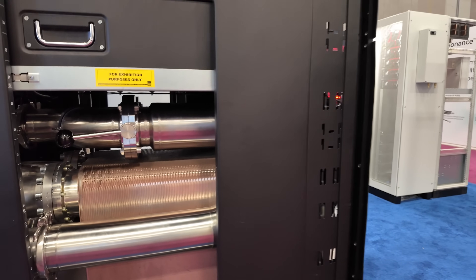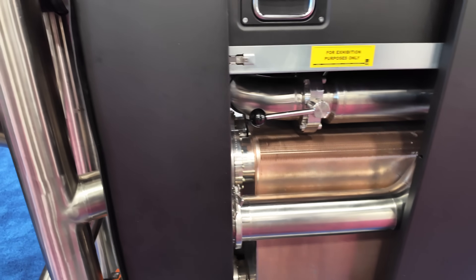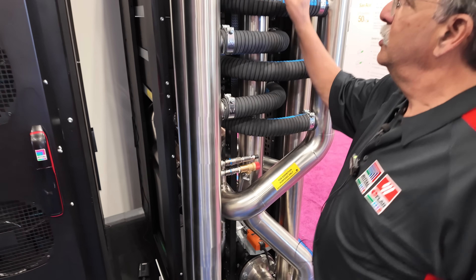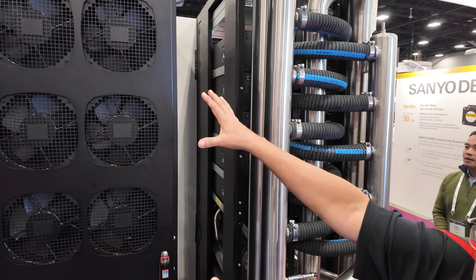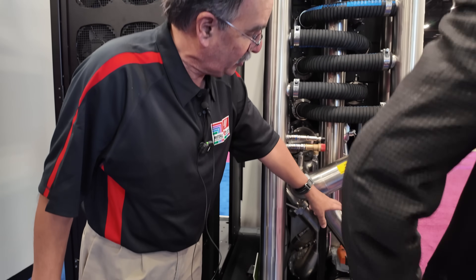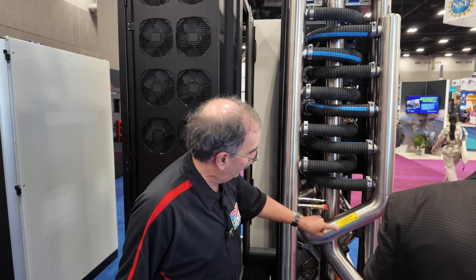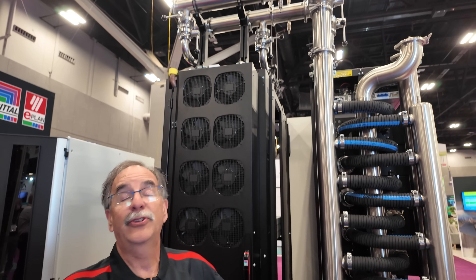What we're looking at here on the back side is the water distribution manifold. The water distribution manifold supports water distribution out to the individual footprints, supporting the heat removal requirements at the chip level, coming into a manifold that provides the technology water on one side, pumping it back to the water-to-water heat exchanger. That is the facility water — the heat coming out of here, transferred to this water through the pumping units, through the heat exchanger and out. All of that heat is going out to facility and ultimately to atmosphere.